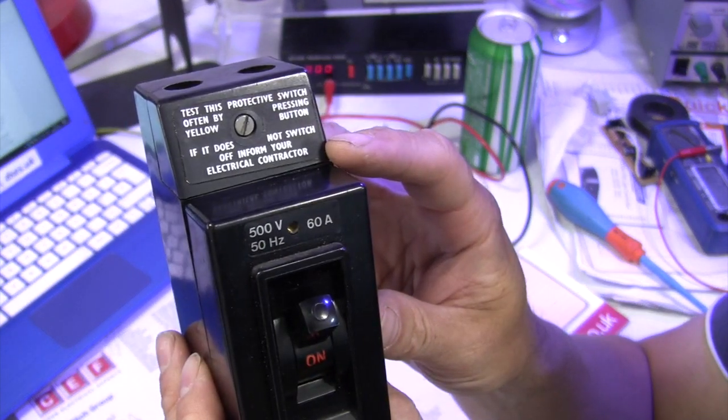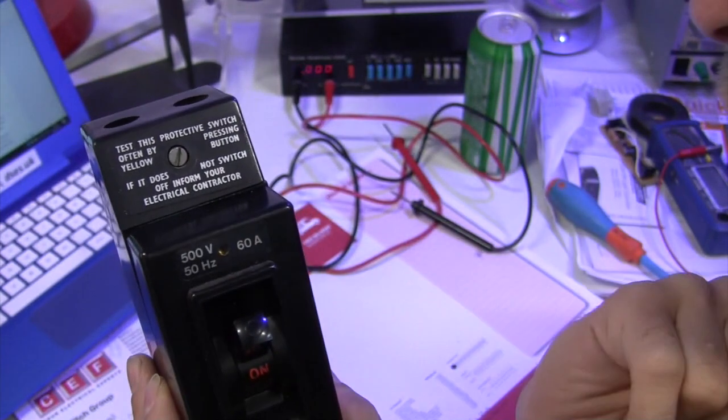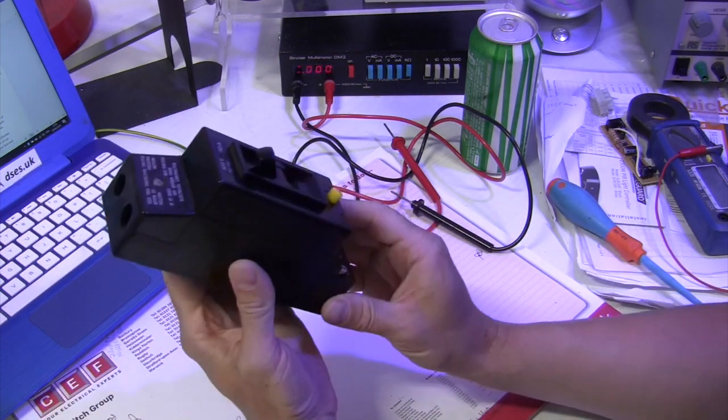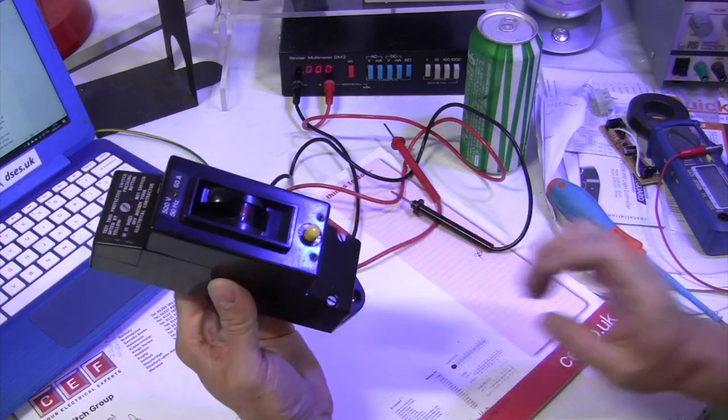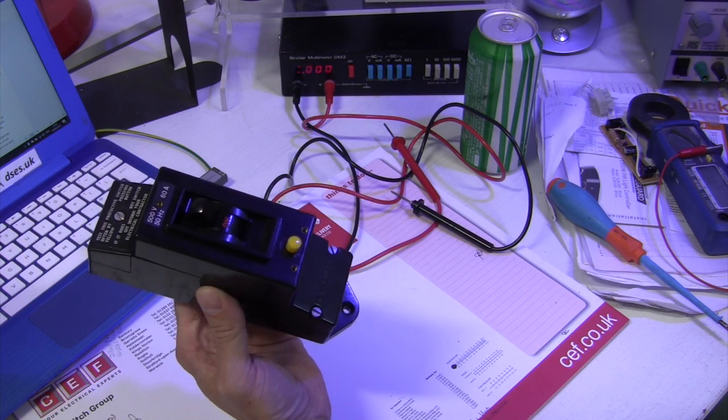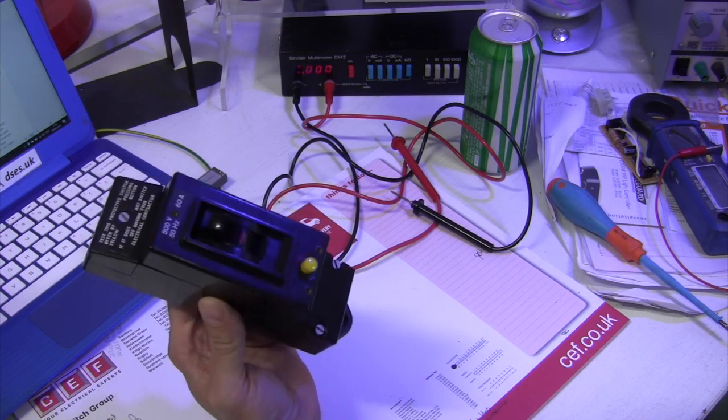advising the homeowner that they should inform their electrical contractor should the test button fail to operate. This particular example was sourced from a decommissioned TT installation dating back to 1980, which has now been converted to PME.